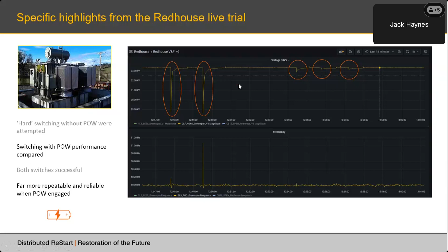But then when we utilized the point on wave, as demonstrated by the 3 switches in the orange circles on the right-hand side there, you can see that the voltage deviation is almost negligible, only pulling it down in the worst case to about 32.8 or so kV. So the point on wave was a really effective device that we utilized for the duration of the tests. Whilst we did have some issues and trips as a consequence of either under frequency or under voltage when not utilizing the point on wave, we were always successful when utilizing the point on wave relay. So I think it points to the fact that if DERs are going to reliably and securely contribute to a distribution restoration zone, having a point on wave relay installed is certainly something that should be encouraged. And it's quite plain to see the results on this slide.